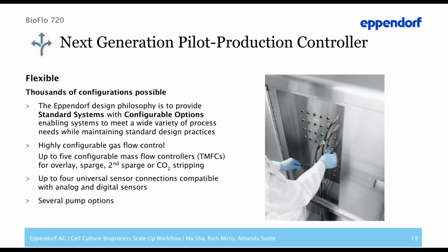Looking at the third principle, flexibility, the general Eppendorf design philosophy provides standard systems with configurable options. And this allows us to design a standard control system and meet the benefits of standard design practices while enabling the ability to configure it in thousands, actually, of different permutations. A couple of examples: the highly configurable gas flow options. Up to 5 configurable TMFCs, thermal mass flow controllers, can be selected for the overlay, the sparge, an optional second sparge, or a CO2 stripping. And those TMFCs can be configured and mixed and matched at different flows to meet the preference or the demands of the specific application or process.